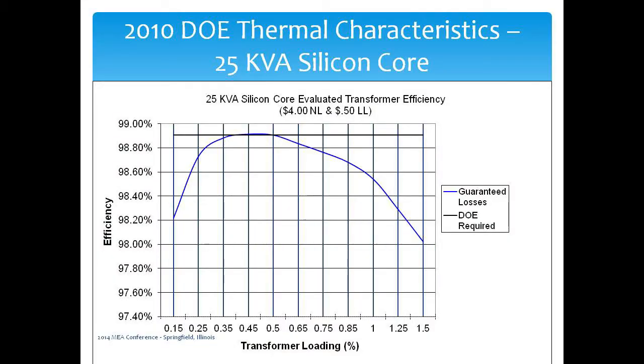And most manufacturers can supply that. If you look at certain designs, just have them look at 25, 50, 75, 100% load, and also have them look at 110% overvoltage. That way, when you look at overvoltage, it'll tell you if your loss watts start to jump 30, 40, 50%, you know that you don't have as much material in it. You shouldn't see that much of a shift on it.